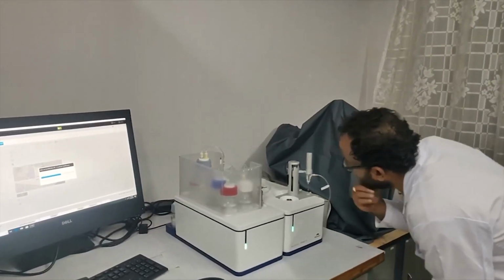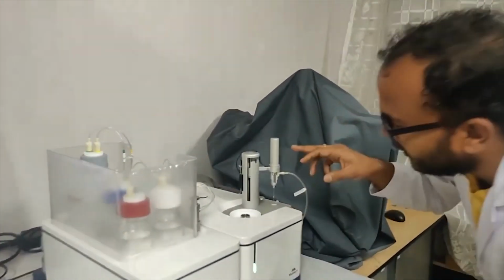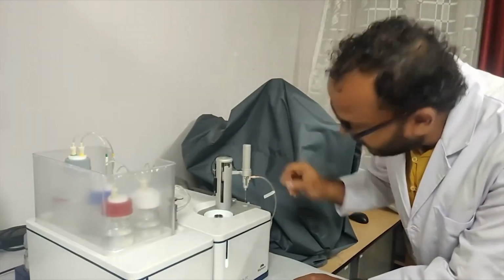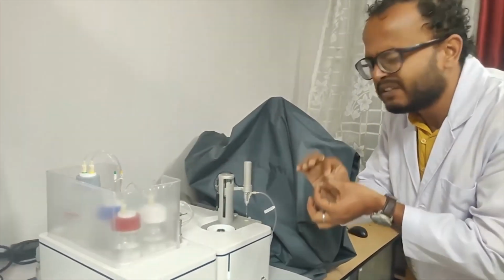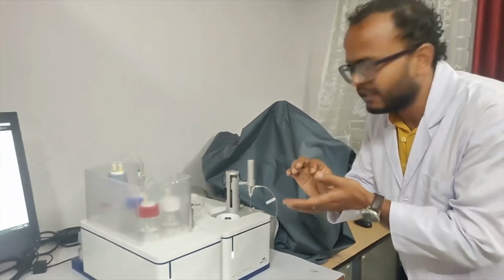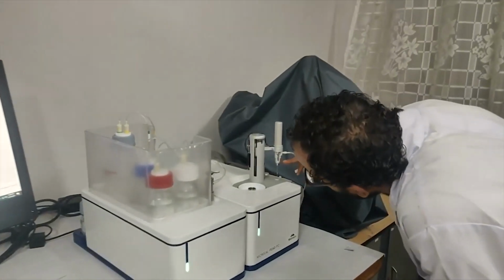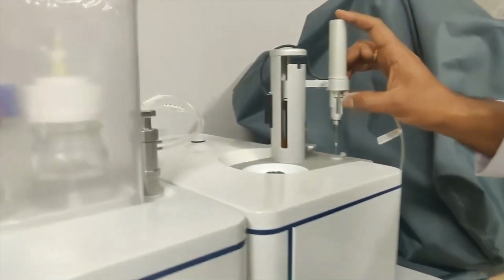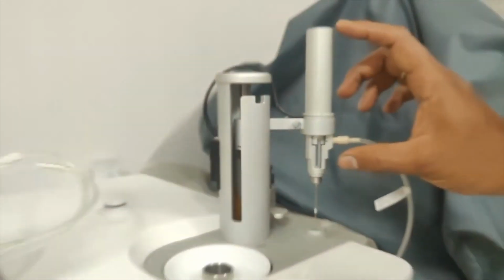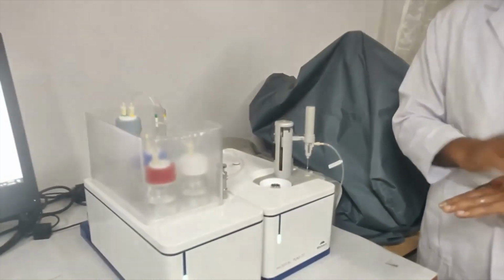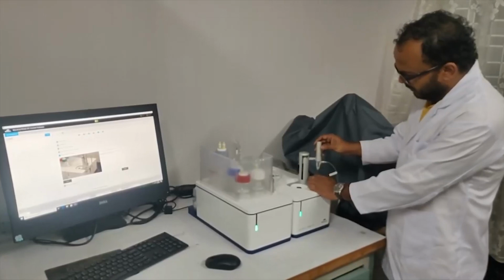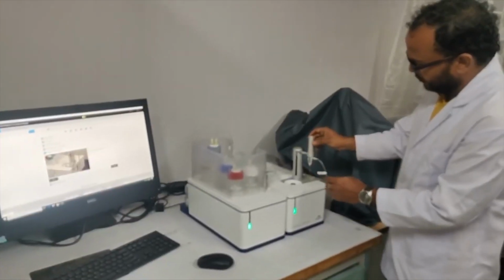Here we have to ensure that while refilling there should not be any gap between the plunger of this syringe and our ligand solution, because that gap may introduce air bubbles later. Now we can see there is no gap between that white plunger and our ligand solution. So the ligand is now loaded into the syringe, and now we have to bring it to the rest position.